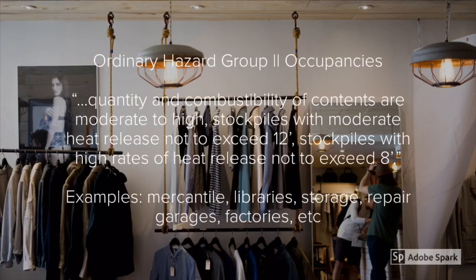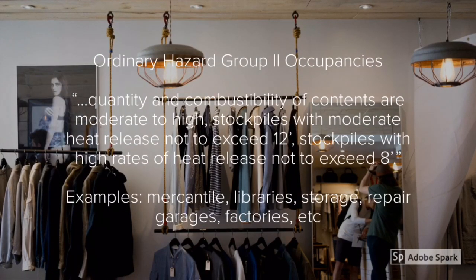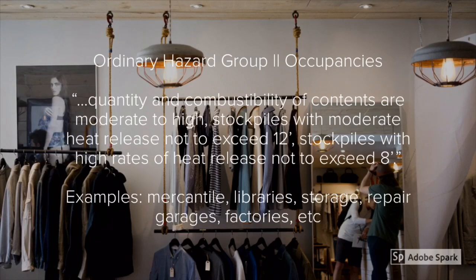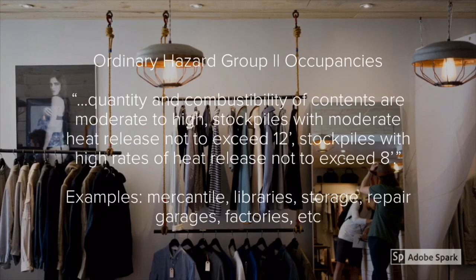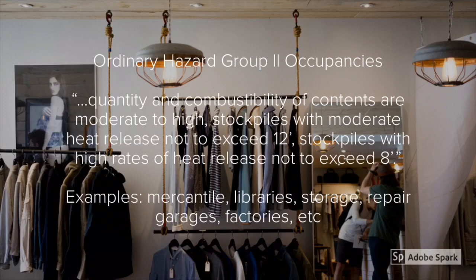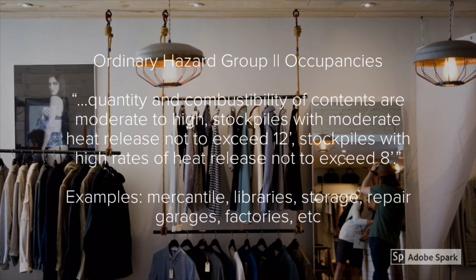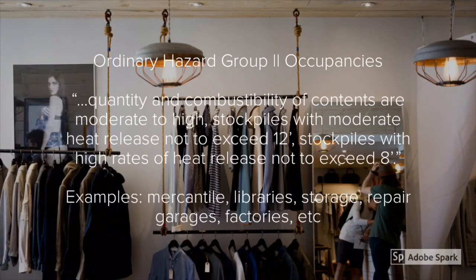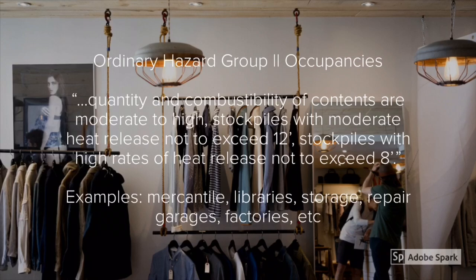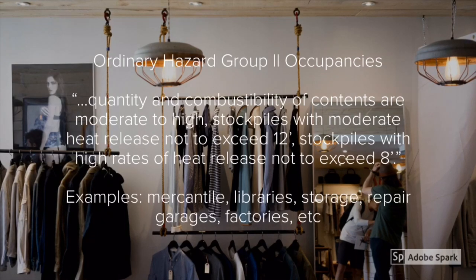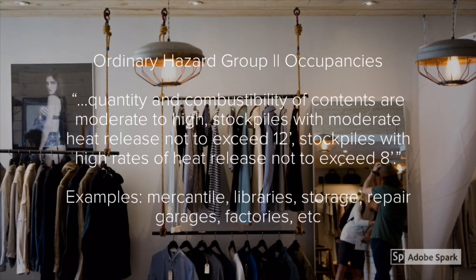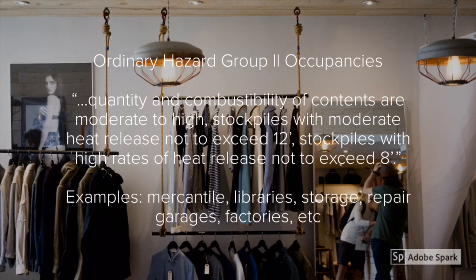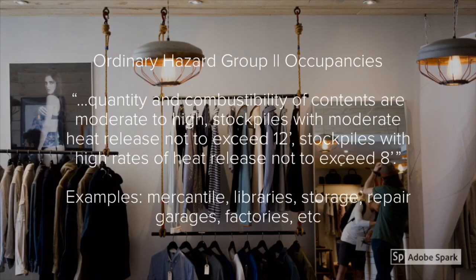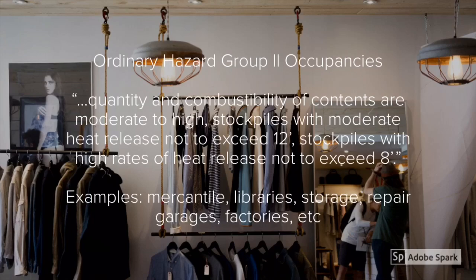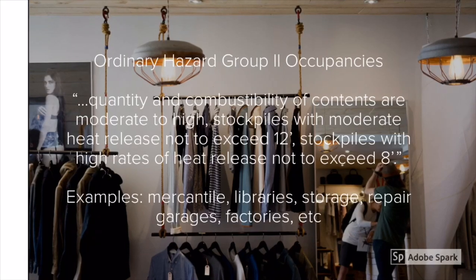According to NFPA 13, ordinary hazard group 2 occupancies have quantity and/or combustibility of contents that are moderate to high, stockpiles with moderate heat release not to exceed 12 feet, and stockpiles with high rates of heat release not to exceed 8 feet. Some examples are mercantile, library, storage, etc. So our example of mercantile or retail would be ordinary hazard group 2 according to NFPA 13.